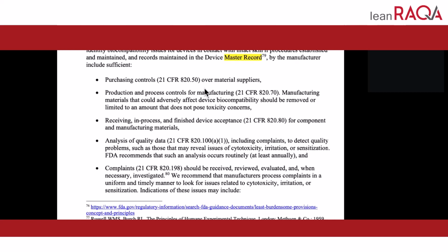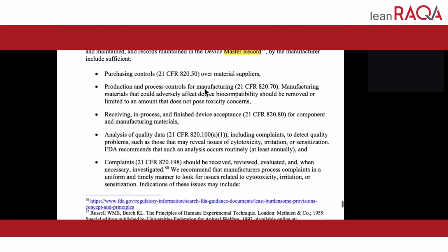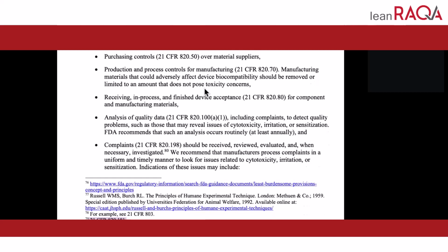Now, the other bullet points, purchasing controls. You are required, according to 21 CFR 820.50, to have an agreement with your supplier that says they'll notify you of changes, and you have to do a risk assessment of those changes before you let them do it. So if Dow Corning says we're going to change the formulation of silicone for you, oh, that's not good, because now I have to change everything in our testing to make sure the new material will pass. I also need to make sure that it'll have the same physical properties now that you made this change. And that's part of the reason why companies that make implant grade material don't make changes. They don't even want to change the packaging or the label on it. So that's number one on the list.